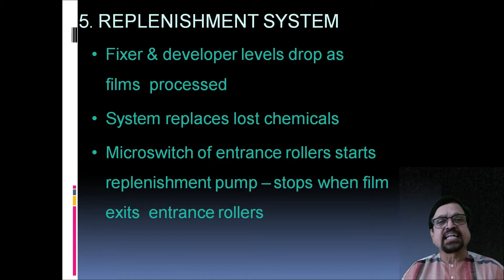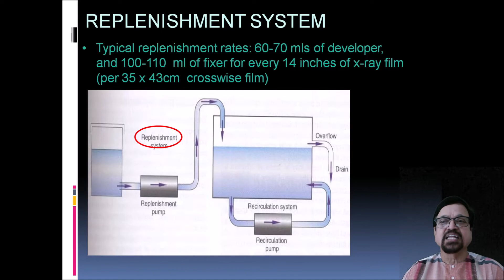The micro switch of the entrance roller starts the replenishment pump and stops it when the film exits the entrance rollers. So this is all an automatic process. This is the replenishment system. In a typical replenishment system, 60 to 70 ml of developer and 100 to 110 ml of fixer are used for every 14-inch X-ray film. It's an approximation, but somehow it works.